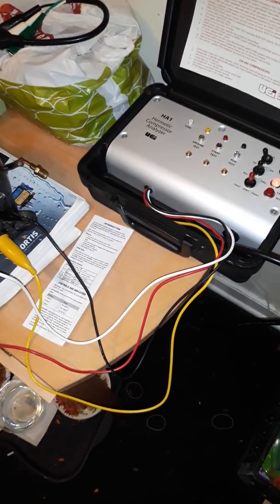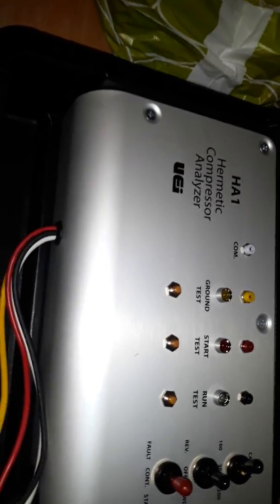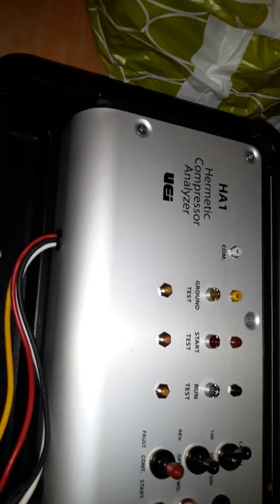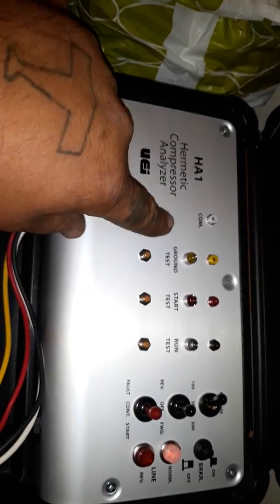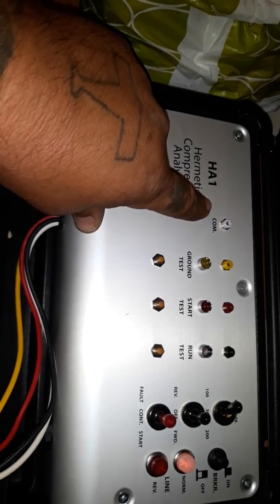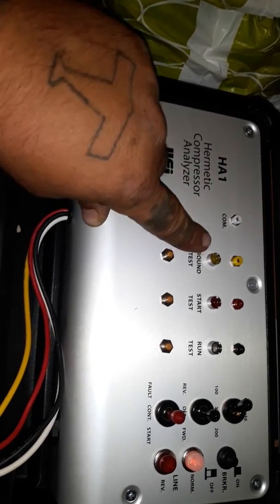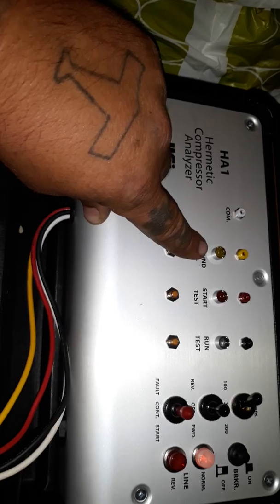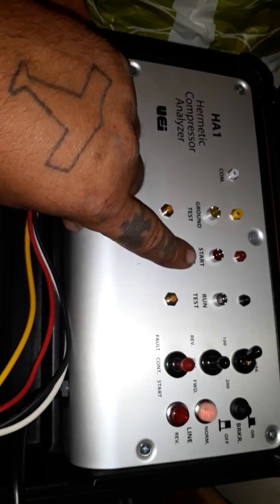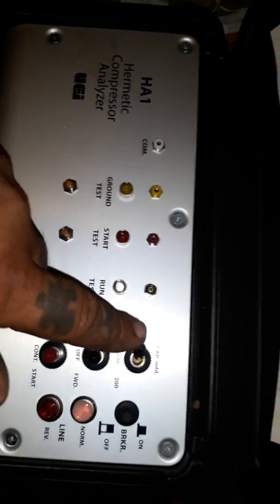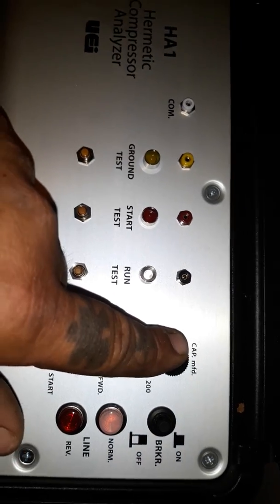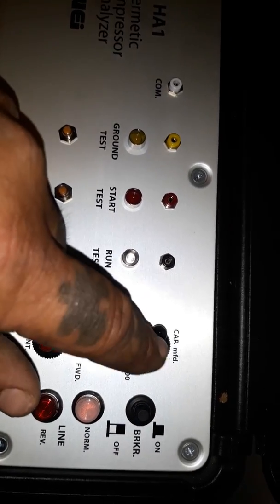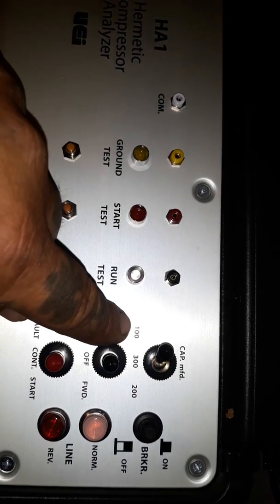Alright, so here is the UEI hermetic compressor analyzer: common, ground, start, and run. This up here replaces your start capacitor. Right now it's all the way over, so it's at 100 microfarads.